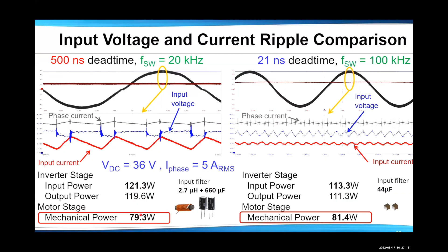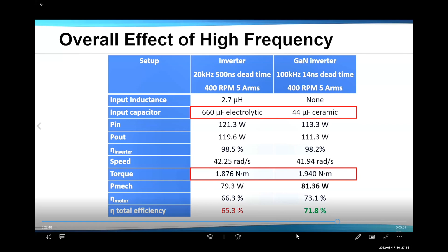So let's look at a more comprehensive table where we measure the input power. We have a system with an electrolytic capacitor on the left, 500 nanosecond dead time, 20 kilohertz, running 400 RPM, 5 amps RMS. And on the right, we have 100 kilohertz, actually 21 nanosecond dead time, 400 RPM, 5 amps RMS. The most important thing to consider is not really the inverter, which is getting more efficient.